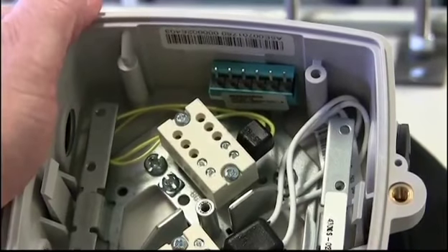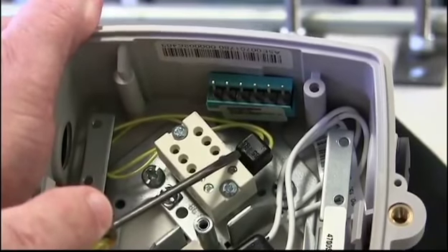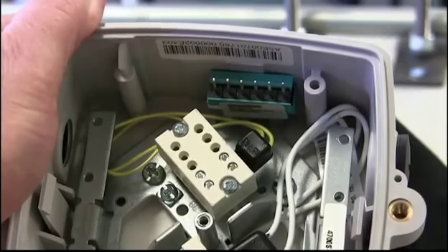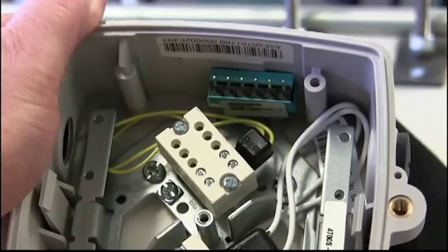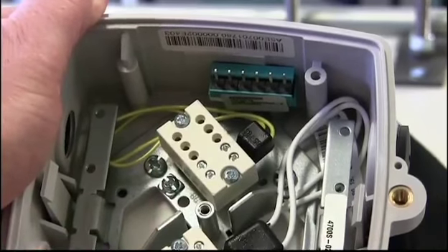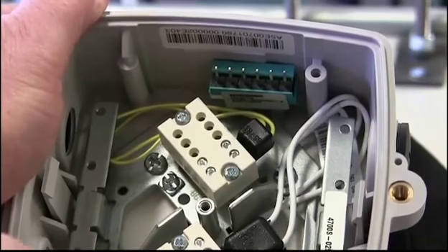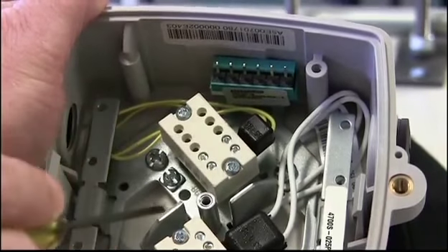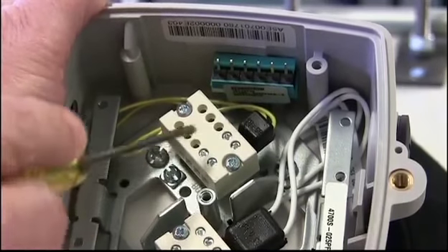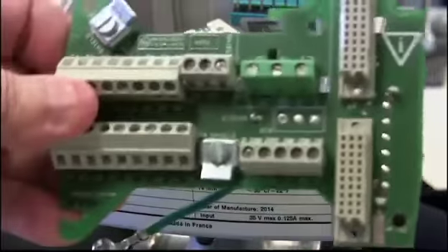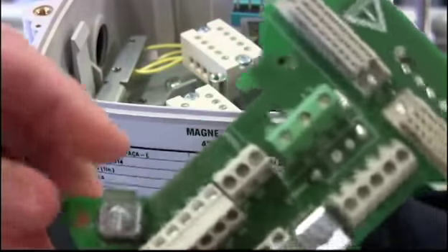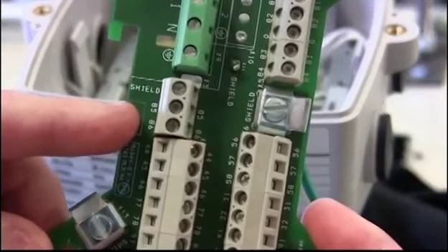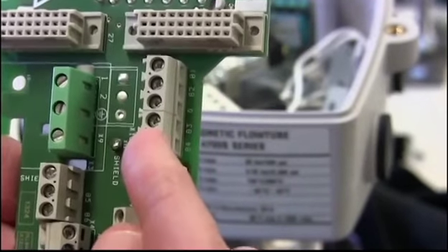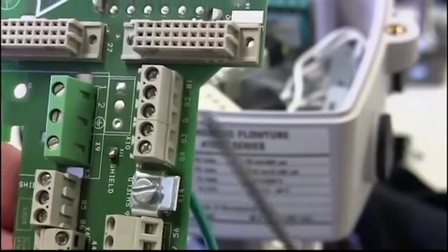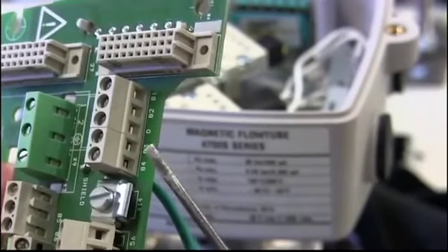What we're going to want to do is remove the coil terminal here and the signal terminal here, and you notice that there are numbers that are embossed on these terminals. On the signal, you'll notice there is a 82, a 0, and an 83, and on the coil it's 86 and 85. Those numbers will correspond to numbers that are on the connector board. So the coil will be placed here, 85 and 86, and on this side the signal connector will come up and get placed in here between 82, 0, and 83.